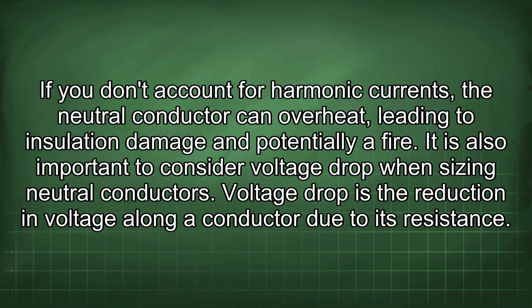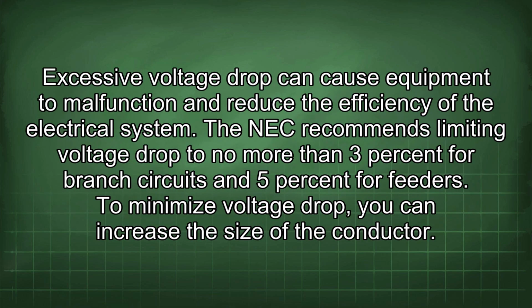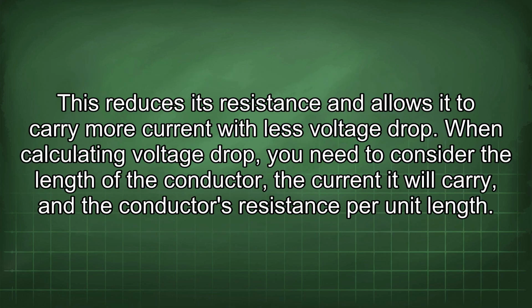It is also important to consider voltage drop when sizing neutral conductors. Voltage drop is the reduction in voltage along a conductor due to its resistance. Excessive voltage drop can cause equipment to malfunction and reduce the efficiency of the electrical system. The NEC recommends limiting voltage drop to no more than 3% for branch circuits and 5% for feeders. To minimize voltage drop, you can increase the size of the conductor. This reduces its resistance and allows it to carry more current with less voltage drop.